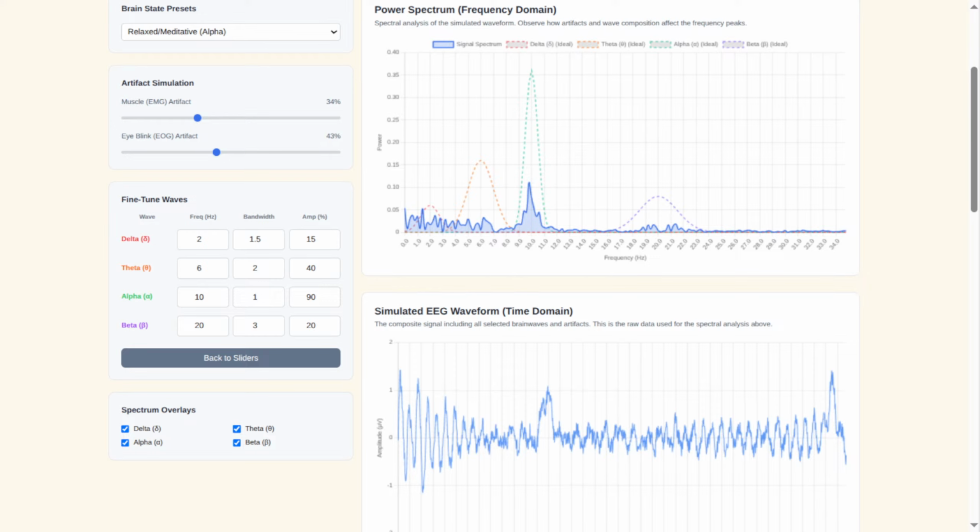Okay, so break that down. What else is in this chain? Well, it starts right at the patient, with the hardware. The electrodes themselves, what they're made of, their size, shape, that matters. Then the cables carrying the signal, the preamplifiers that boost that tiny brain signal, because it is tiny. And then the analog to digital converters. That's the bit that turns the brain's smooth, continuous electrical waves into numbers a computer can understand.